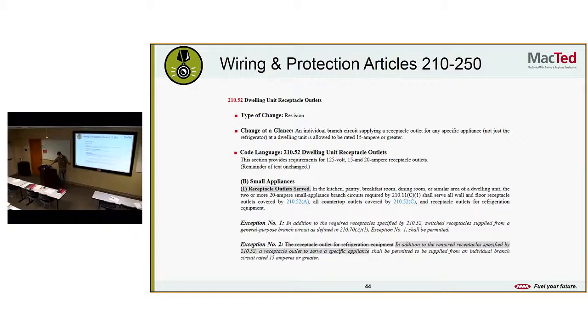And so what was the change here? Receptacle outlets in the kitchen, pantry, breakfast room, dining room, or other similar area of a dwelling unit: 2 or more 20 amp small appliance branch circuits required by 210.11 shall serve all wall and floor receptacle outlets covered by 210.52, countertop outlets covered by 210.52, and receptacle outlets for refrigeration equipment. There's an exception: in addition to the required receptacles, switched receptacles supplied from a general purpose branch circuit. So you can have a switched circuit, probably for your garbage disposal. That's what it sounds like. They're giving some exceptions so you don't have to do a bunch of dedicated circuits for everything in your kitchen.